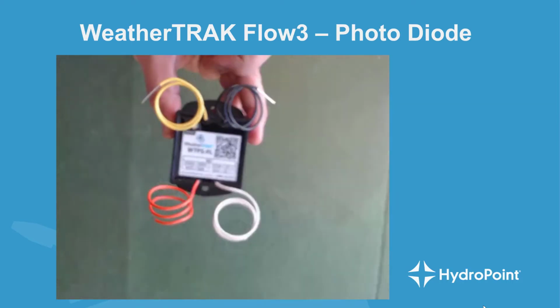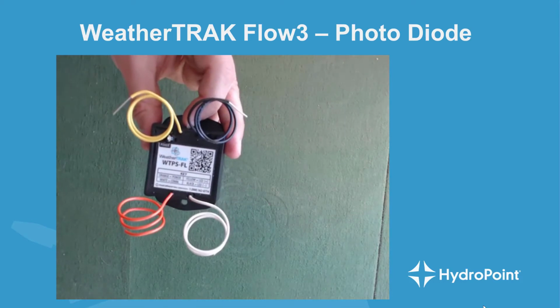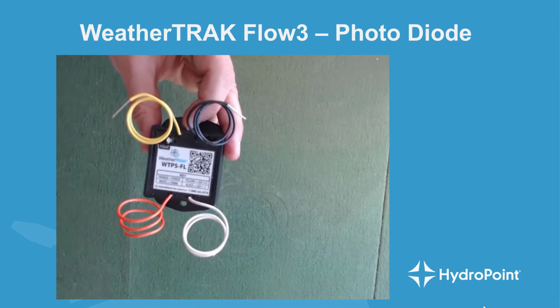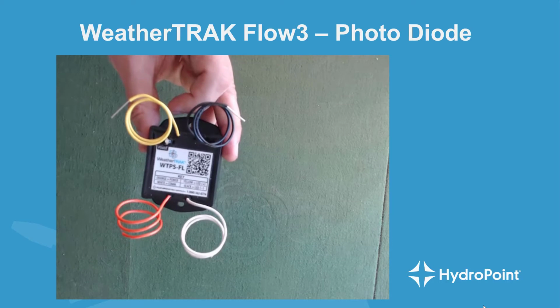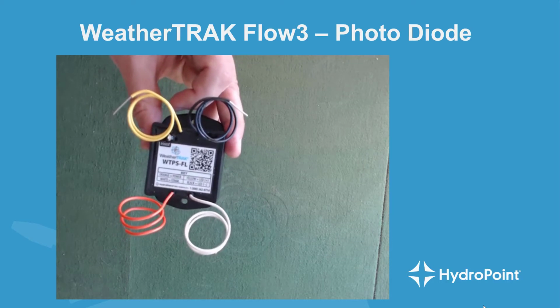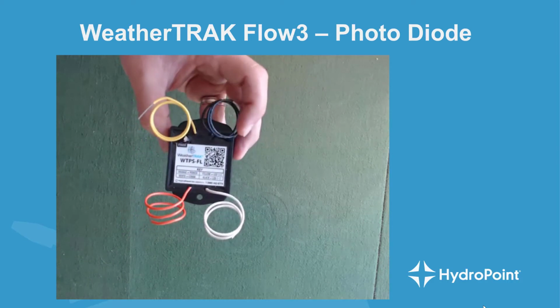If this power supply isn't correctly wired up, it can irreparably damage the meter head. And if the warranty review reveals that the meter was wired up without the power supply, the damage is not covered under warranty.